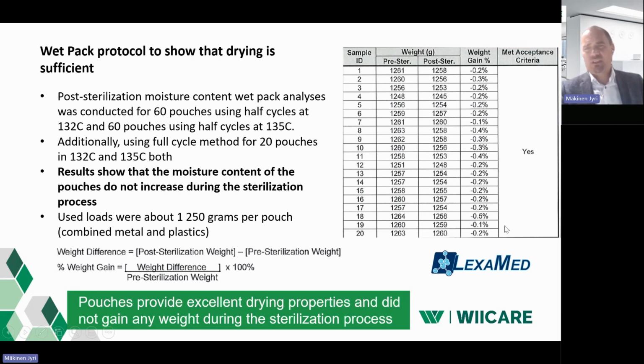And when looking at some of the results, I took one picture of the testing table, where the weight gain was actually negative, so there was a minor reduction of the weight during the process. This is probably because there is always some moisture content in the paper, and when you sterilize it in the drying period, this moisture content goes slightly down, and that could be a reason for that. Maybe some of those plastics could also affect that somehow. But really good news. So these provide excellent drying properties, and it's safe to use these for packing instruments in the hospitals. This is really the worst case that you see here.